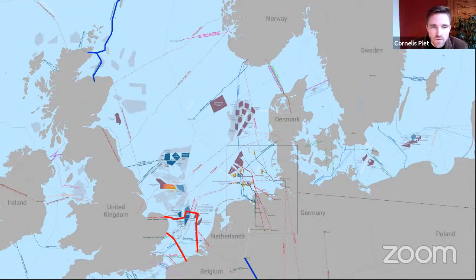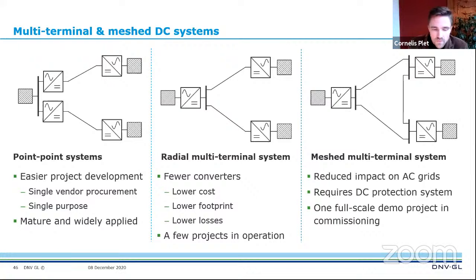So what is the difference? Can you go to the next slide, please? On the left, you see point-to-point, an HVDC system made out of two point-to-point systems. This is often referred to as radial systems, where you have converters on each line end. This is the paradigm for HVDC grid building today. The reason for this is that you have generally easier project development with only one single vendor delivering both converter stations, one single purpose, and each link can be optimized for its application.